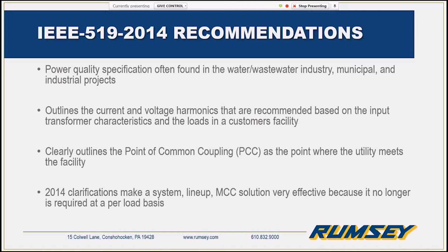So it opens up the playbook for all of you when you're in design to say what's most cost and what's most space effective for me here. Is it at the load, or is it at the MCC, or is it at the switchgear? And that opens the door very nicely for an active filter being able to correct for all the loads that are downstream of it at one point.